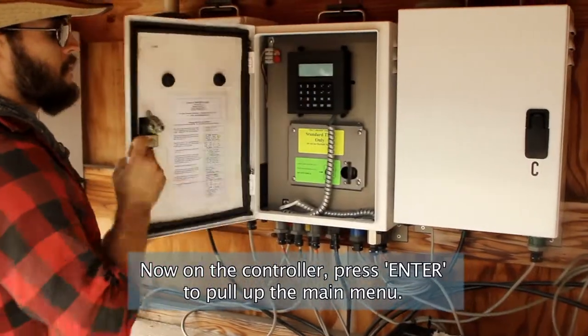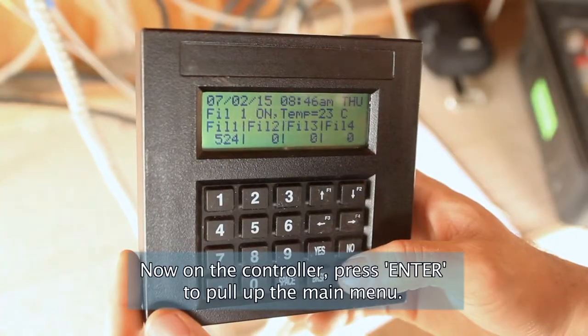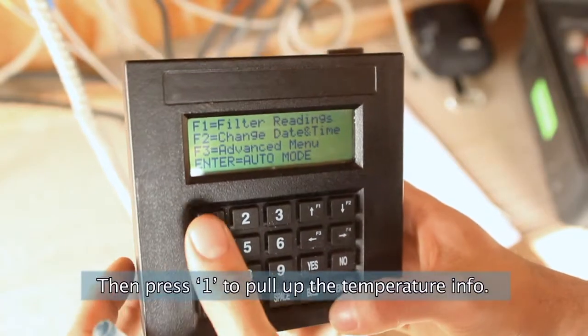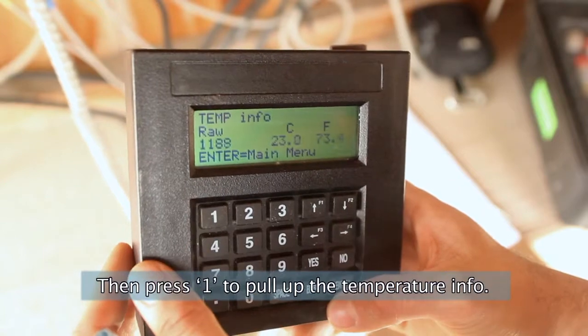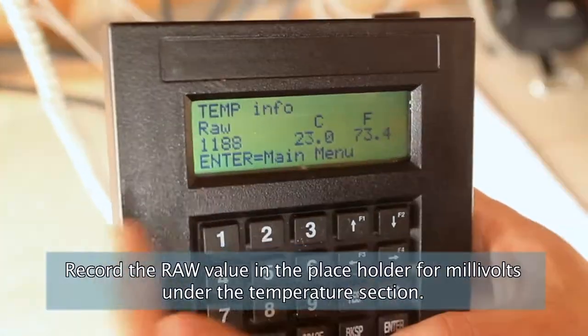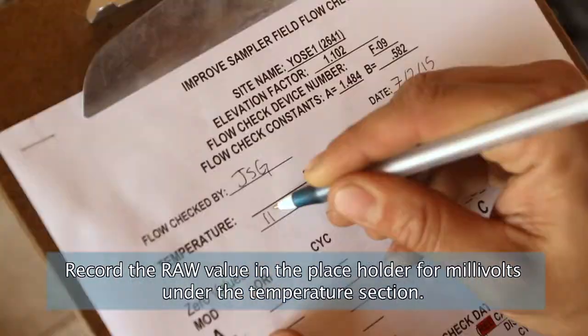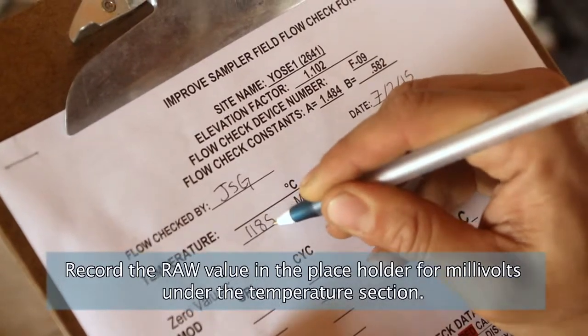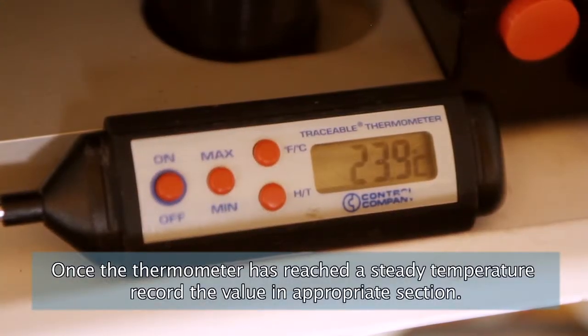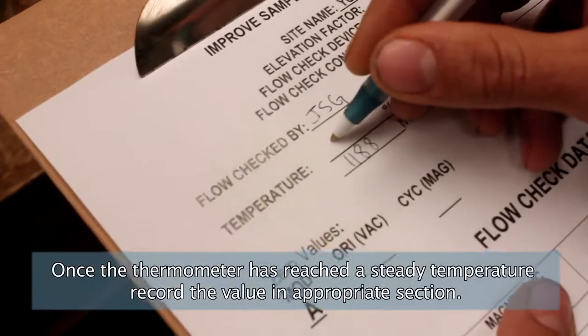Now on the controller, press Enter to pull up the main menu. Then press 1 to pull up the temperature info. Record the raw value in the placeholder for millivolts under the temperature section. Once the thermometer has reached a steady temperature, record the value in the appropriate section.